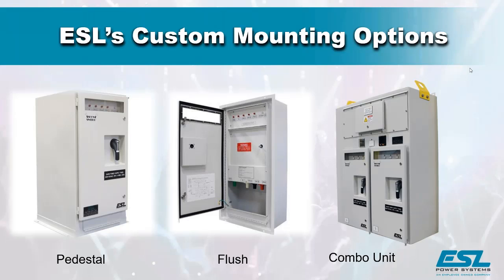Is there a way to put a label on the outside of the unit so you can see the circuit breaker ratings, amp ratings, KA ratings, and maybe even the settings, so you don't have to open the door to get to the breaker? Yes, as a matter of fact, on the left unit, the pad mount unit, in the lower left, the nameplate has all of the ratings engraved directly into it. The one underneath the handle, that large black nameplate, says shore power supply, 200 amps, and calls up the voltage 208Y 120. So all that information is directly on the outside of the switch and can be readily seen without gaining access to the inside.